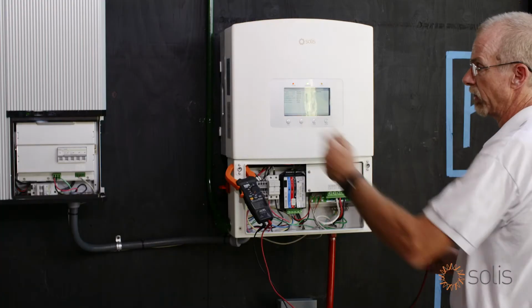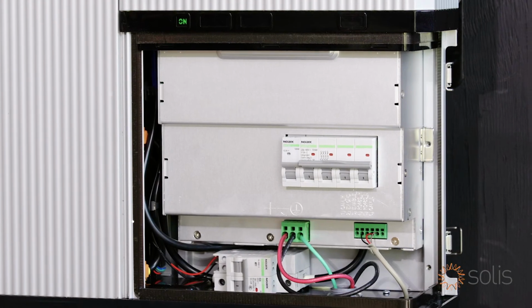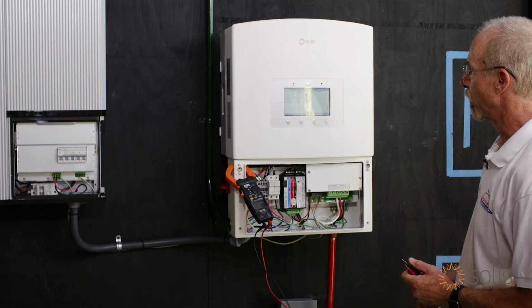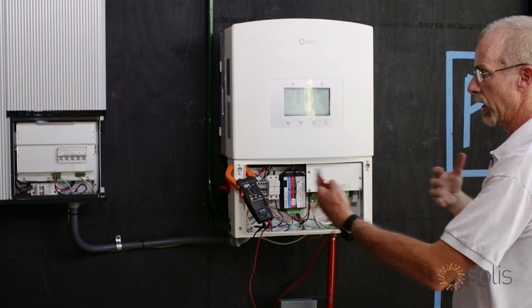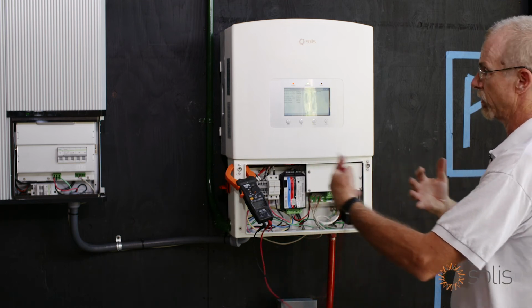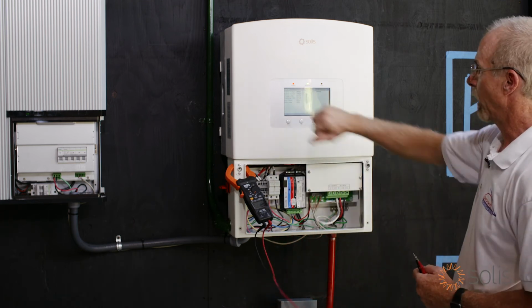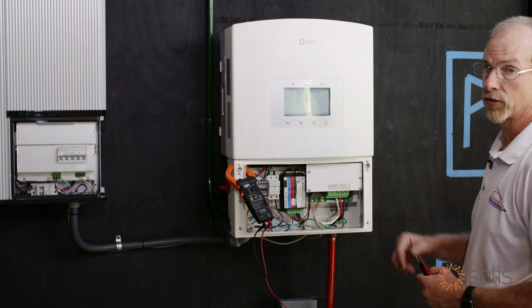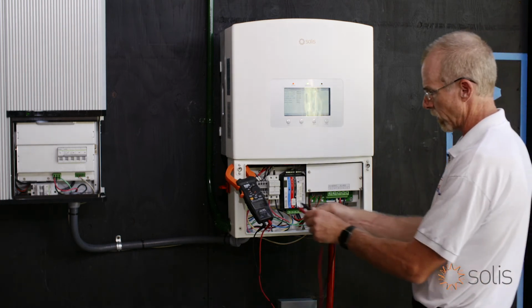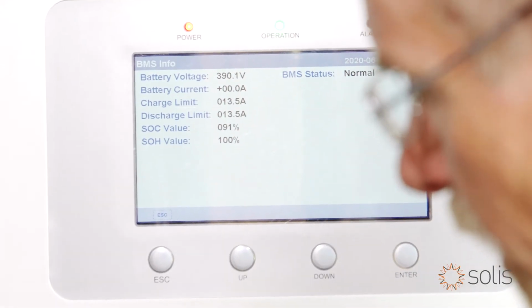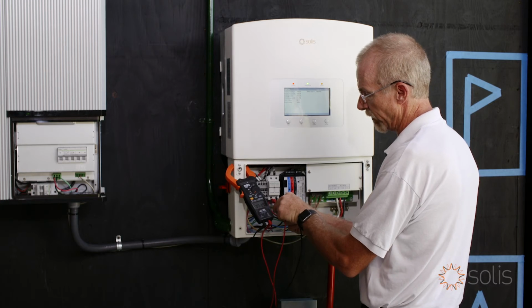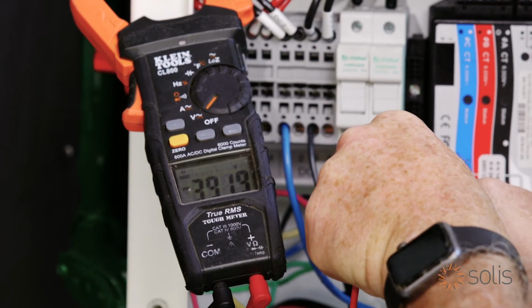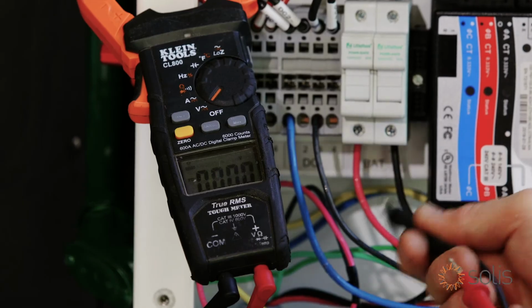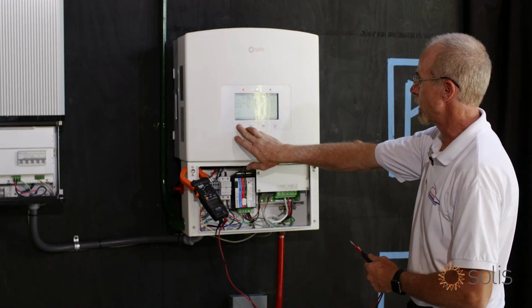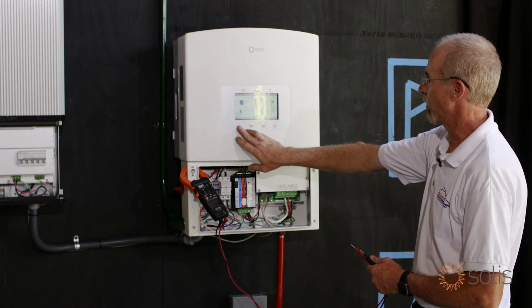As soon as I close this in, I hear something over there. Now the battery voltage is accurate because now the communications are happening. We have the electronics talking to one another, and now we settle in on the correct voltage, which is 392. So this test we did before does help you make sure you got polarity correct - you can visually see that.